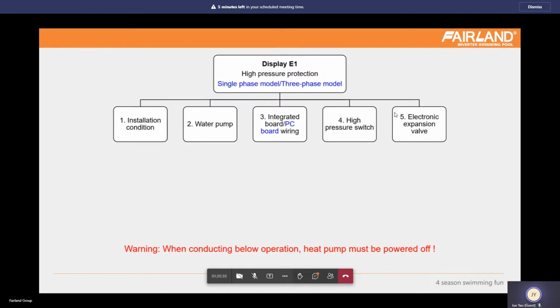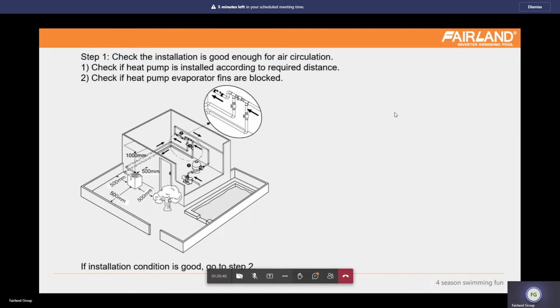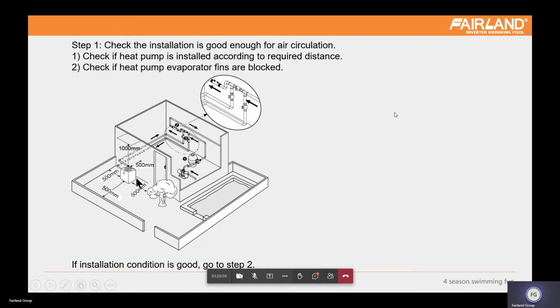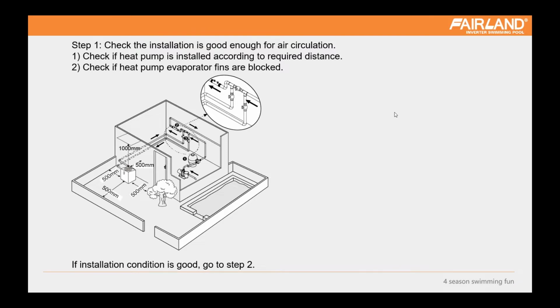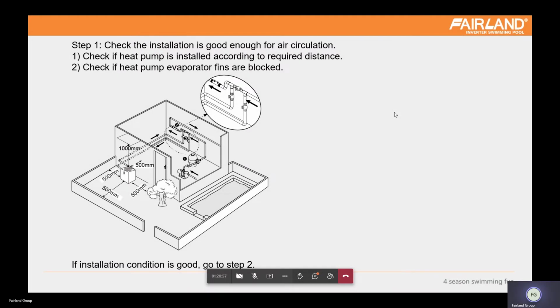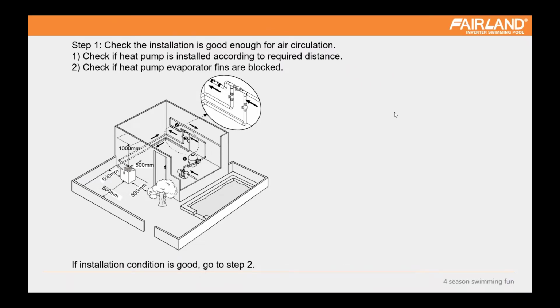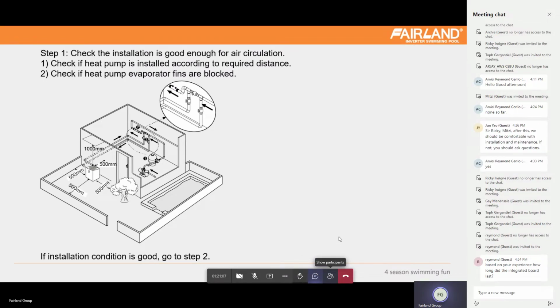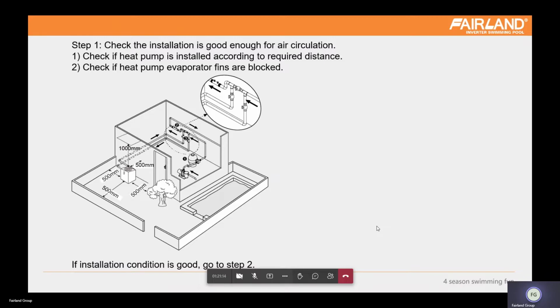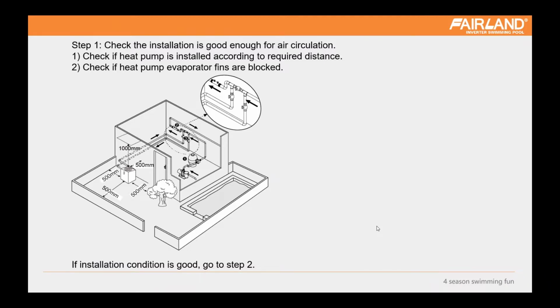For E1 high pressure protection, we will check from this first step. Normally, we check that the installation is good enough for air circulation and ventilation. If it is not set in a closed space or very bad space, then ignore it. It is always fine, because even if the air ventilation is bad, it is difficult to cause E1. It will cause other problems, like the heating capacity becoming smaller. So that is easy to check.